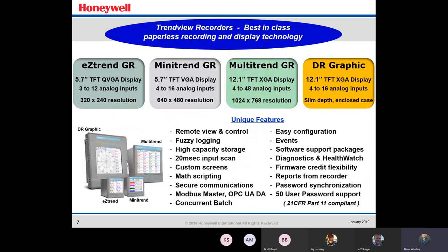We've got best-in-class paperless recording and display technology here with the TrendView recorders. Starting with the eZtrend — the smallest model — it has a 5.7-inch display and 3 to 12 analog inputs. The resolution is 320 by 240, as it's the smaller, most cost-efficient model. Moving into the MiniTrend, it has a couple more analog inputs and better resolution — a good option if you want to save space but still need up to 16 inputs.